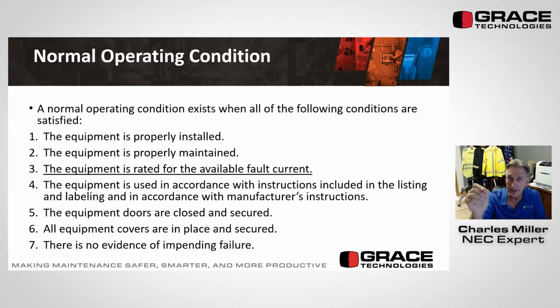If I were to turn that breaker on, I couldn't do it wearing a short sleeve shirt — I'd have to put on a long sleeve shirt just to turn a breaker on or off. Well, the committee came out with 'normal operating condition.' If all of these conditions are satisfied, then no PPE at all is required. Until this coming edition, if this change goes through, there were only 6 conditions.